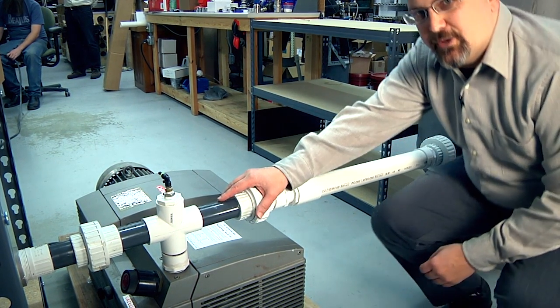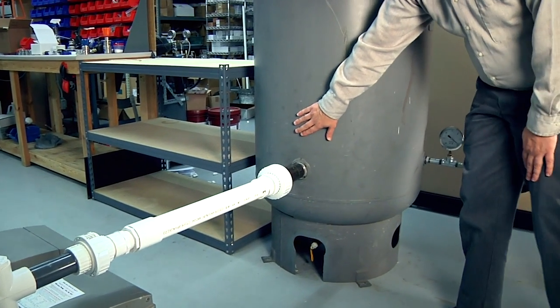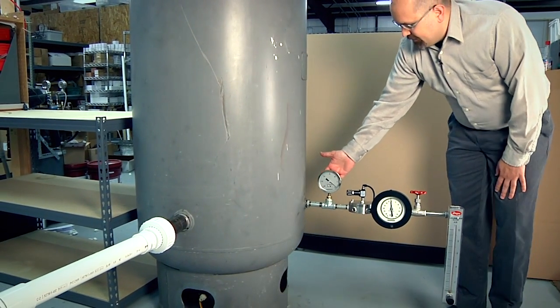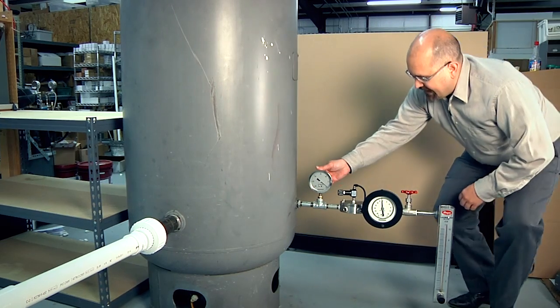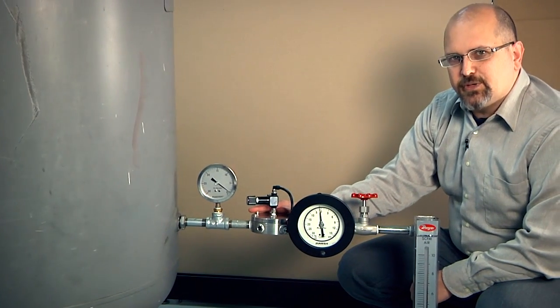This 5 horsepower vacuum pump is going to feed a vacuum reservoir tank, and coming out of this vacuum reservoir tank we've got a vacuum gauge that shows us how much vacuum supply we have and also an Equilibar high flow vacuum pressure regulator.